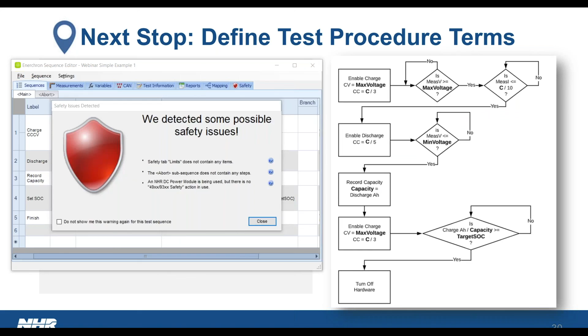As we were talking about that robust process, the next step was to define the abort conditions. These are global, or even down to the individual step—is there anything where we should say, let's stop? Examples could be: does a step take too long, or is it never completing, so maybe we want to stop the test? Or have we measured an unsafe voltage, current, or power—too high or too low? If we've tied in the battery management system and it reports a problem with voltage, current, power, temperature, or even a fault code, should that stop the test?